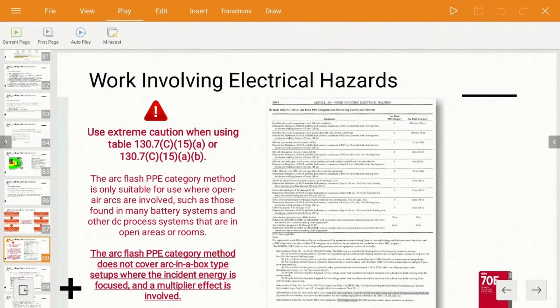But let me tell you something. As far as your table method, this is what the table looks like. The 70E says that this method does not cover an arc in a box type of setup where the incident energy is focused and the multiplier effect is involved. This method is only suitable for open air arcs like battery systems, DC process systems in open rooms. So I always tell people, don't use this table. Go by the analysis method where somebody like an engineer has gone through and done all the calculations and put a label on the equipment. But that's something you learn in qualified person training. Okay? So don't use that.